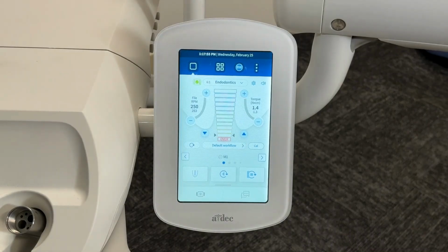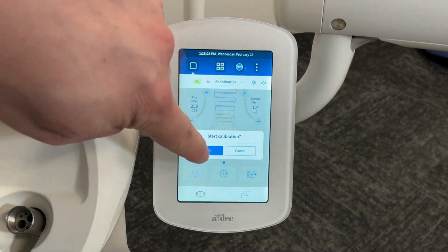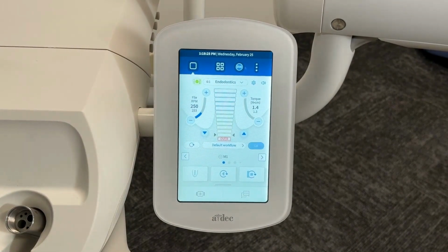To calibrate a handpiece, first lift the handpiece with a file installed from the holder. Then select the calibration button and press start. The motor will engage, spinning the handpiece and file at various speeds to calibrate the motor with the specific handpiece and file currently installed. Once calibration is complete, the calibration button will turn green.